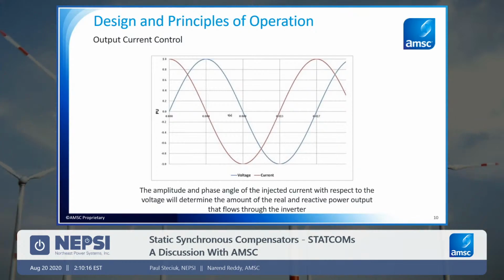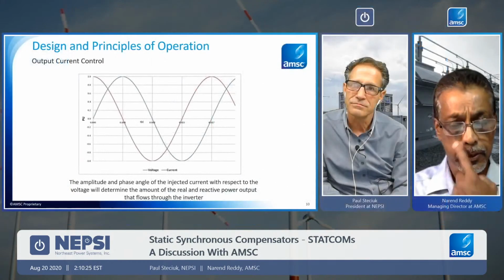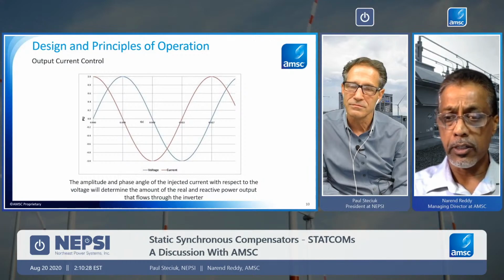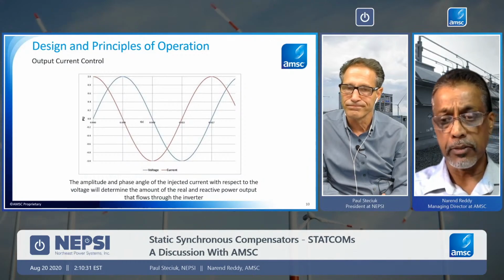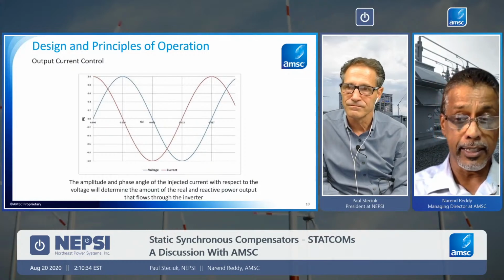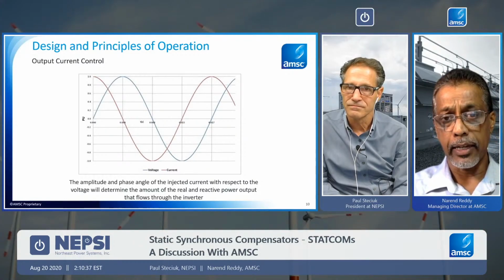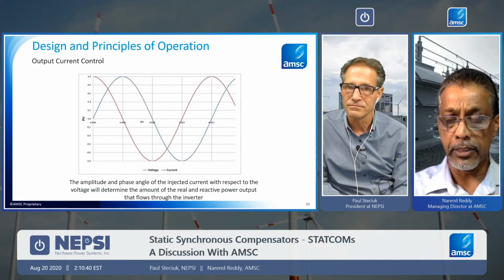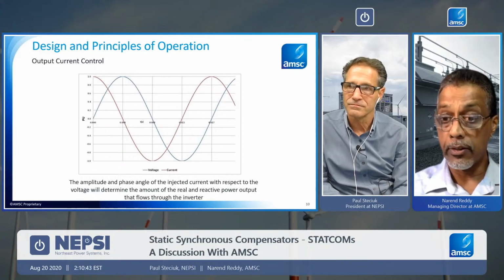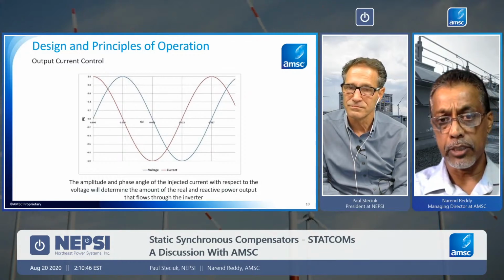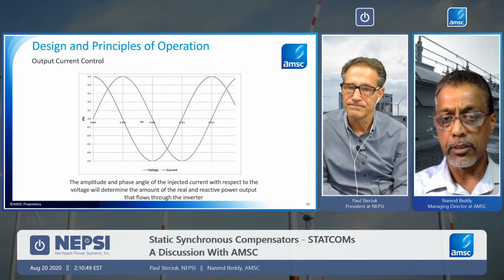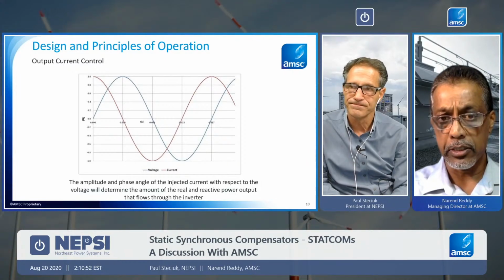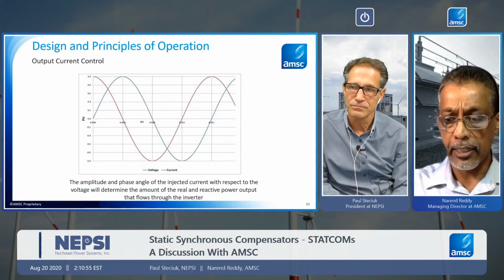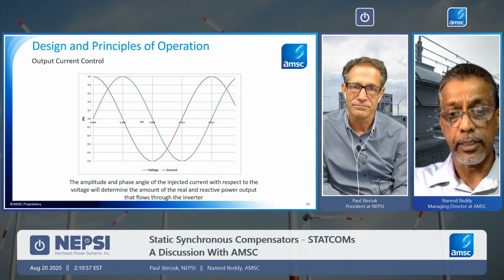It may not be nominal, but there is a voltage at a certain frequency. And the output current from the STATCOM is actually a controlled current output. And that's one of the key differences about a STATCOM: the output current is controlled, and you can control the phase angle of that current with respect to the AC system voltage, either 90 degrees leading or 90 degrees lagging, or you can control the magnitude of that current anywhere from 0 amps to the rated ratings of that inverter. So it is a linear control. There are no step changes or things like that.